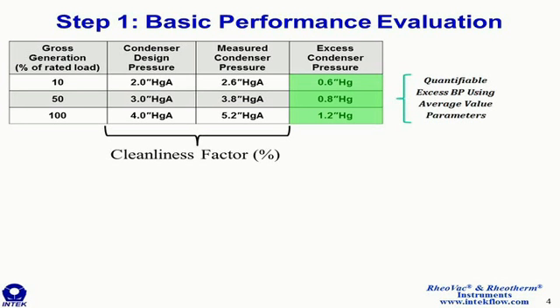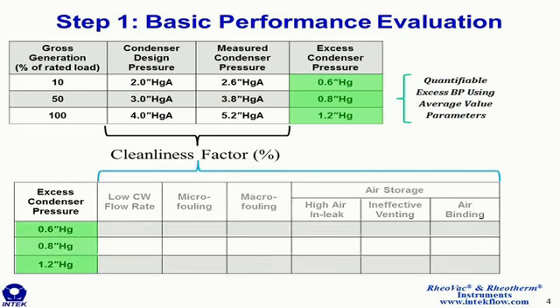These parameters indicate how badly the condenser is performing, but they don't tell you what's causing degraded performance. And even the term cleanliness is a misnomer because there are a lot of things that can cause an indicated low cleanliness factor. We classify performance degradation into these six categories. Fouling, everybody should be familiar with, and how dirty or obstructed tubes can increase condenser pressure. Also, if there's low flow through the condenser, lower than what's being used for the calculation, then you can have an indicated low cleanliness factor.